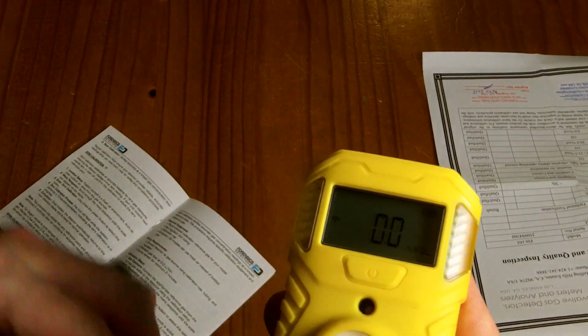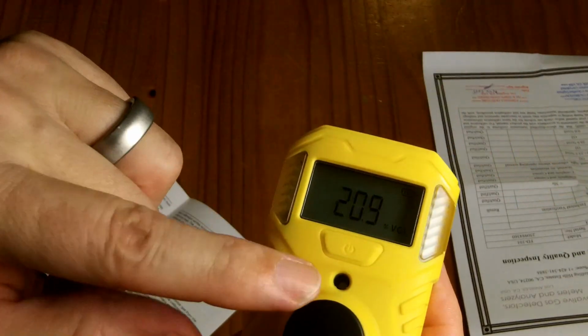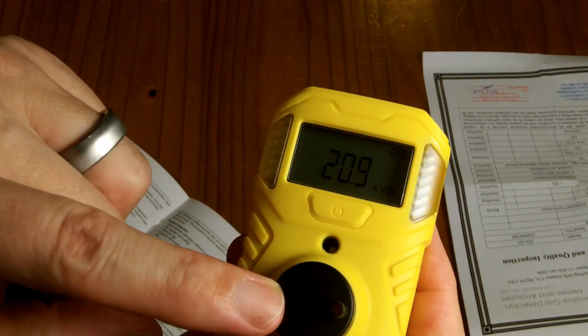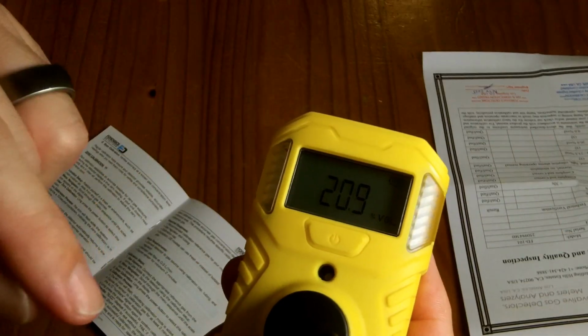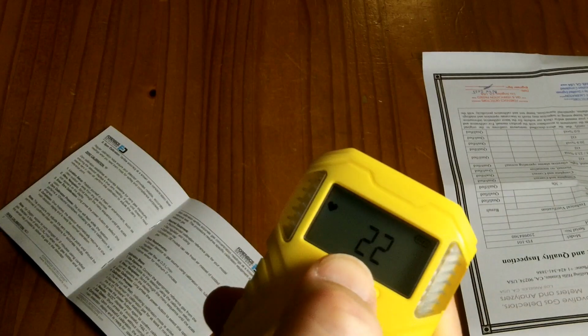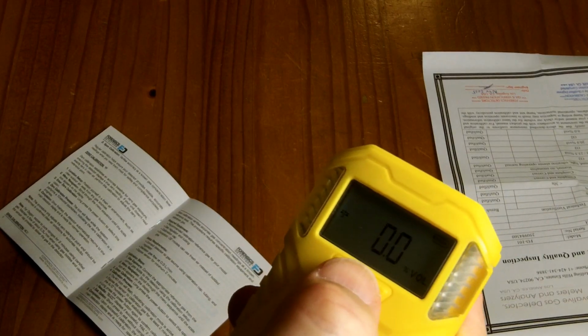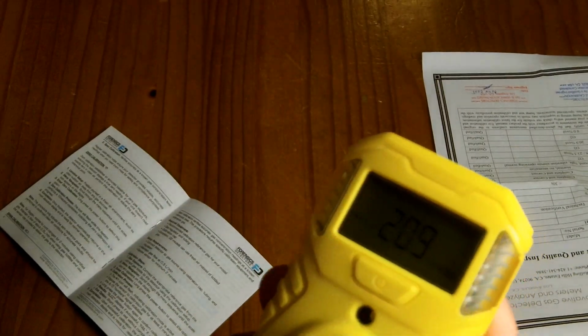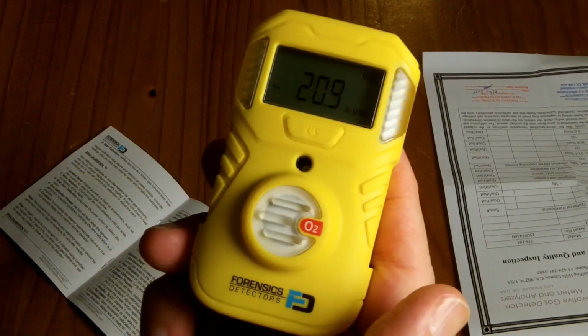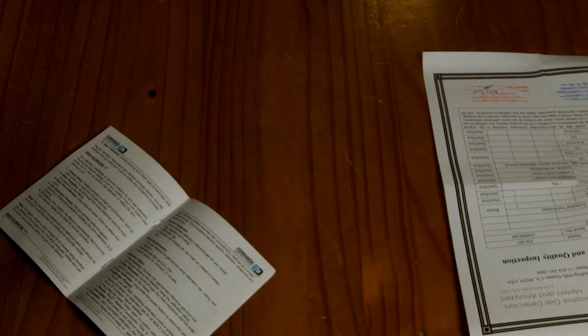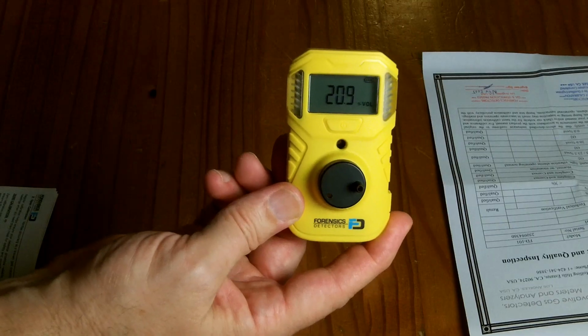So zero calibration is this little icon here. Looks like a balance scale. You basically flow pure nitrogen over this sensor at half a liter per minute for 2 minutes when you go into that mode. Now for the span calibration, that's the icon that looks like, I guess, kind of a little sword. It has a circle with a line coming out of it. You basically just use open air for the oxygen sensor for that. But they say you don't have to calibrate it for the first year.